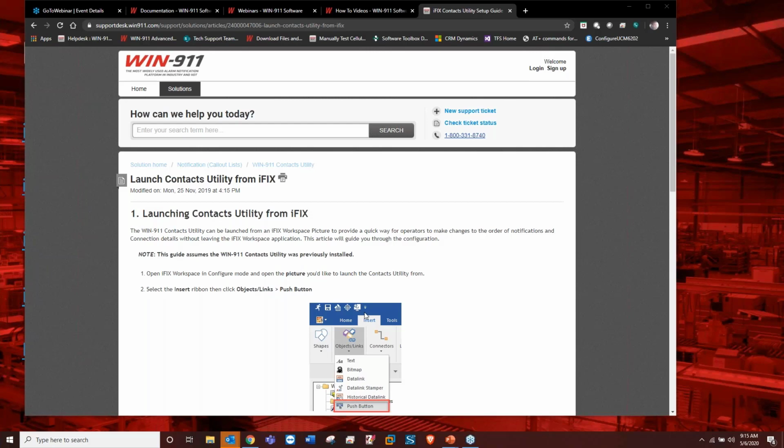I guess to add to that, if you're using imported blocks, you can customize the descriptions in 911. If you're using pages and subscriptions or filters, then we're going to use the properties, the way you lay it out. You have the ability to configure that, but we're going to use your native iFIX description. And we do support the longer tag names and descriptions as well with the latest iFIX versions. Yep. Thanks, Jeremy.